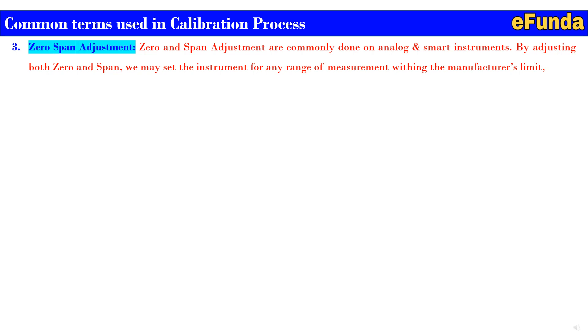Zero and span adjustments are commonly done on analog and smart instruments. By adjusting both zero and span, we may set the instrument to any range within the manufacturer's limits. For most analog instruments, zero and span adjustments are interactive — adjusting one has an effect on the other. For smart instruments, there is no interaction between span and zero adjustment.